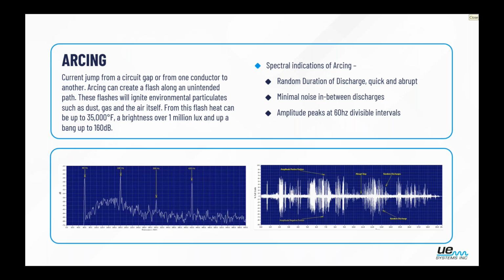Now, the most severe one that we look for, everyone's ideally never going to find, but it is out there, is arcing. So on that one, the frequency, if we do have the discharge, often we will see that 60 hertz line frequency. If you don't see 60 hertz, it's not necessarily not arcing. You can still have that happen, but typically we would see a 60 hertz frequency on spikes, as in this left image. And then on the event over time, random abrupt discharges. So you can see that there is no build up to discharge, it just occurs. It is happening and then it immediately stops and then it starts up again. So probably the most aggressive sound that you would hear, very noticeable snaps and cracks, not much other noise going on unless you had other events occurring at the same time.